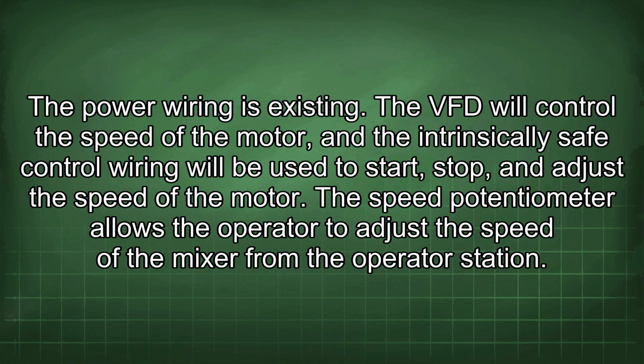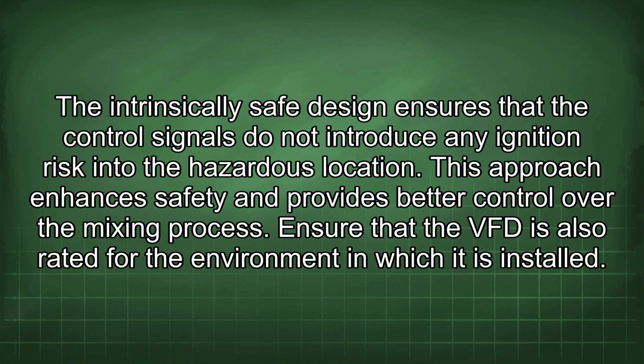The speed potentiometer allows the operator to adjust the speed of the mixer from the operator station. The intrinsically safe design ensures that the control signals do not introduce any ignition risk into the hazardous location. This approach enhances safety and provides better control over the mixing process.